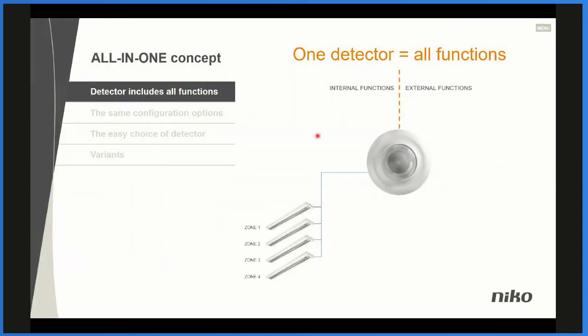The detector, as you see here, has everything included. That means it has the power supply on board, a DALI power supply on board. It has a detector with a lens, a PIR detector. And from the detector, we have a DALI bus. To that DALI bus, we can connect up to 4 different light zones. These light zones could either be daylight control, or non-daylight control, what is called a secondary zone.